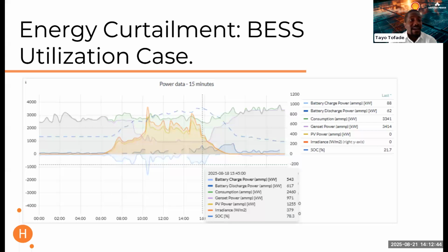Before the introduction of BESS, 5 gensets used to be run, so the load on the gensets would be 2.5 megawatts. But now we've reduced the number of running gensets to 2, so only 1 megawatt on the genset, while solar and BESS take the rest of the load. Solar and BESS integrate with the existing network, which also makes for automation of the genset. It was a manual run of the genset previously. Now the genset starts automatically based on the SOC and the availability of solar, and that makes for automatic operation on the client side too.